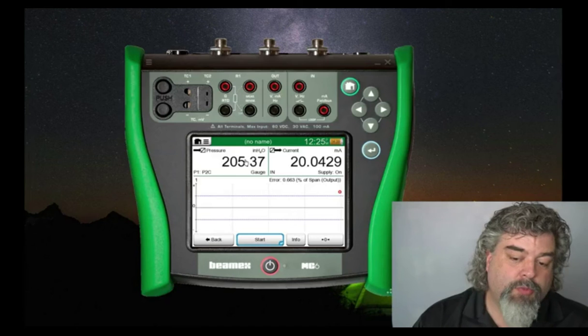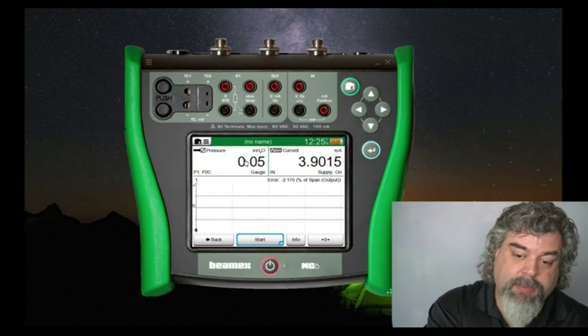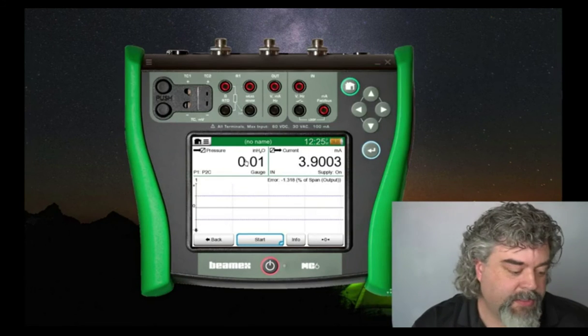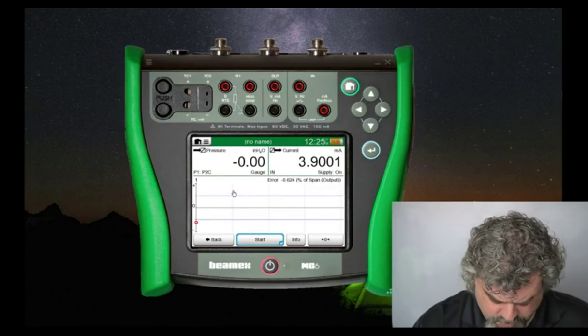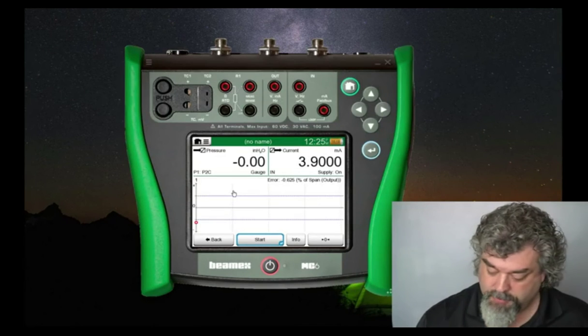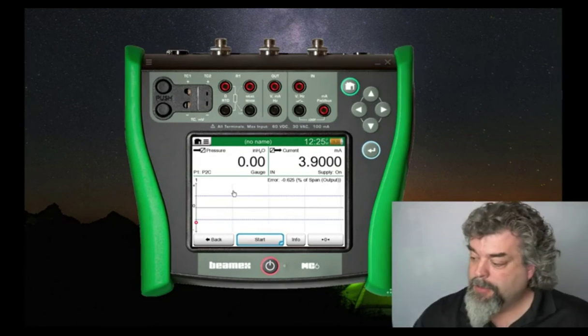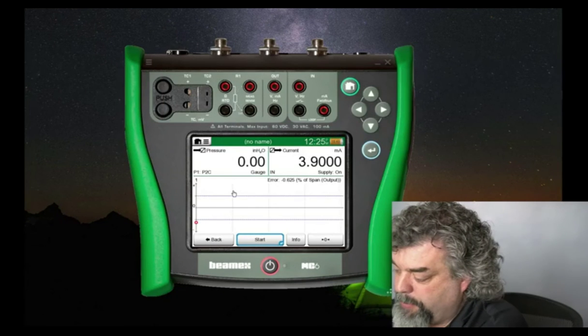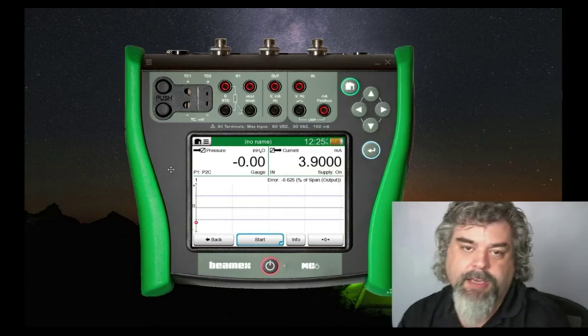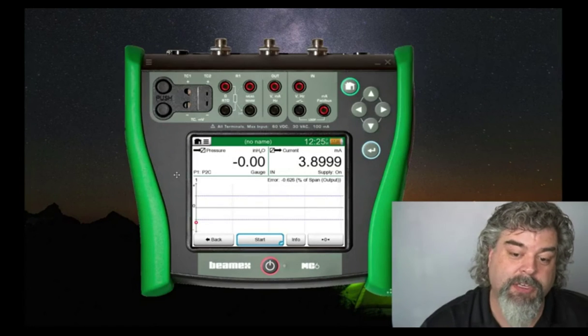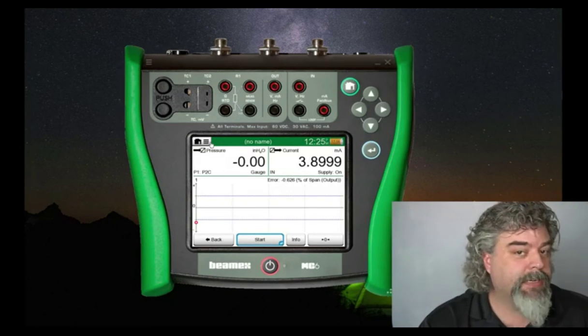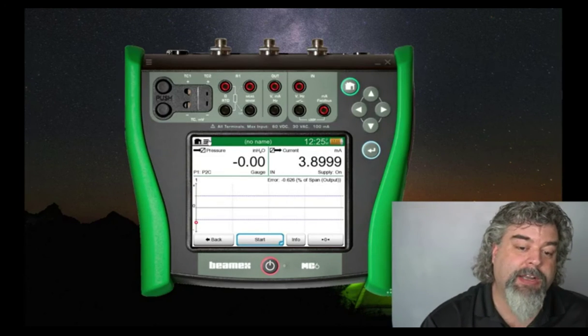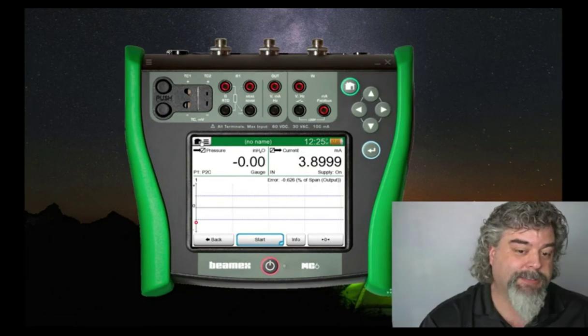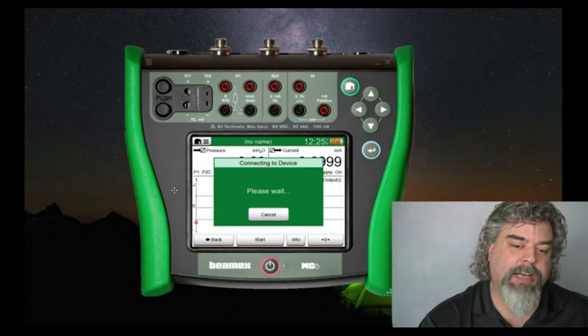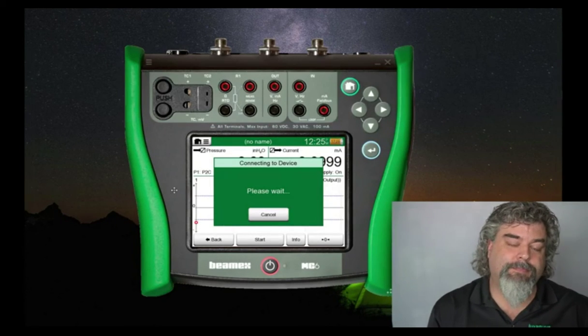All right, now we're ready to do our as left. Let me vent my pressure. But what I need to do is do an adjustment. I just need to figure out where to make the, well, okay, actually this is a HART device and we do it through the communicator. So to fire up the communicator, we bring up the secret button. It's also called the magic button, whatever. The real name is the menu button, but I like the magic button. We'll go with that. Upper left, magic button, start communicator, please wait. Cue elevator music.